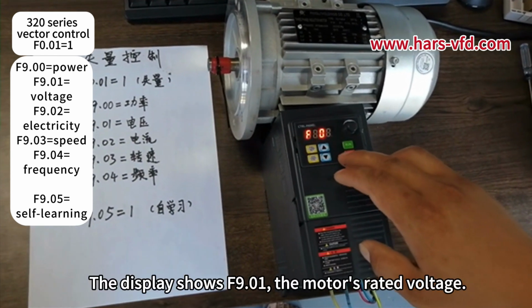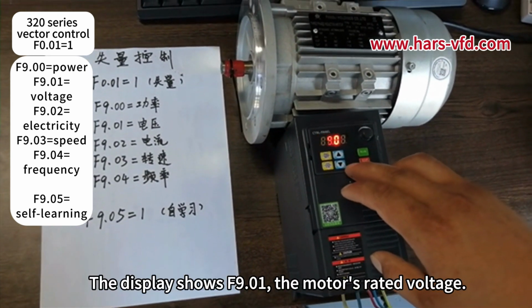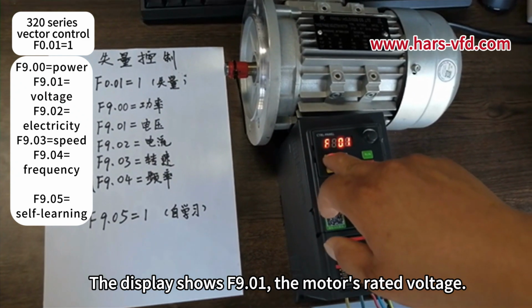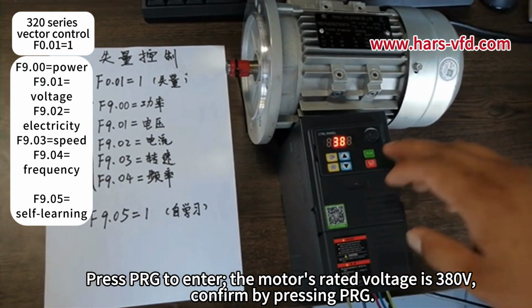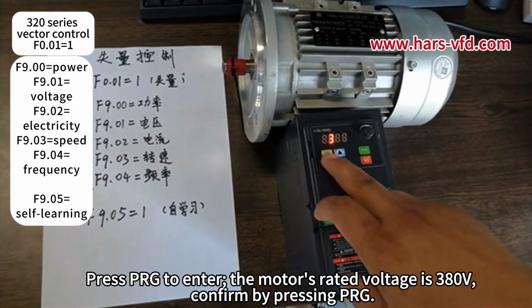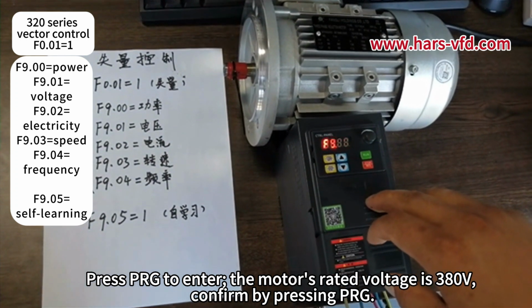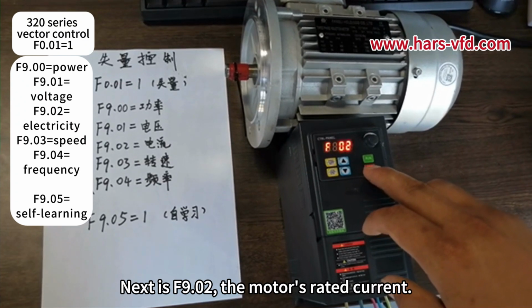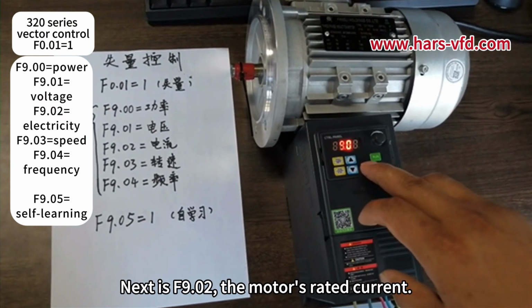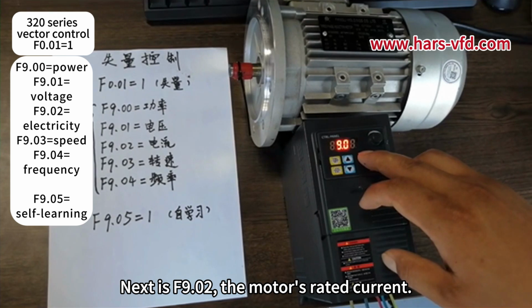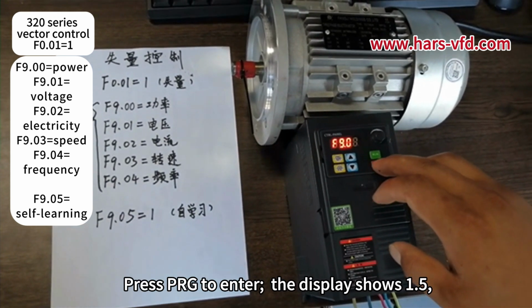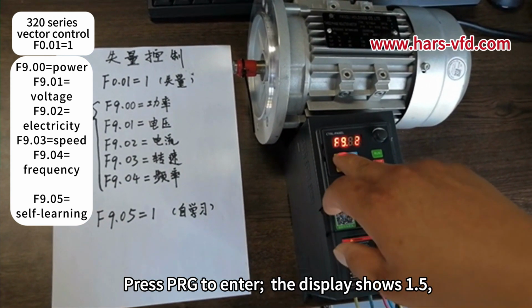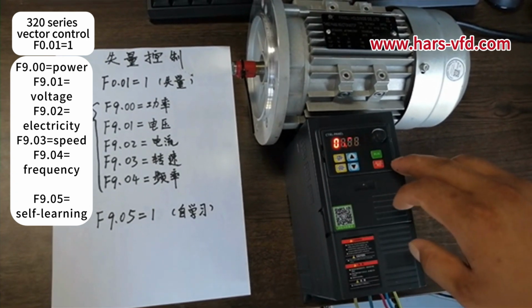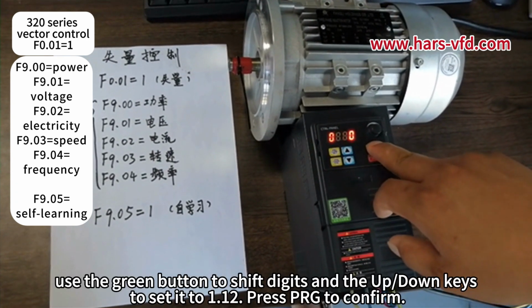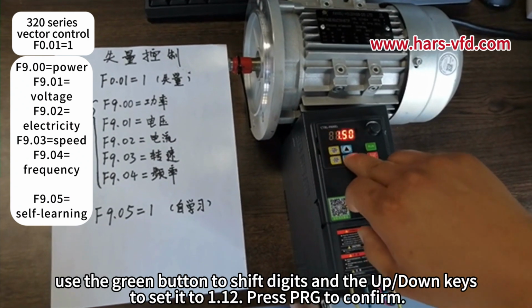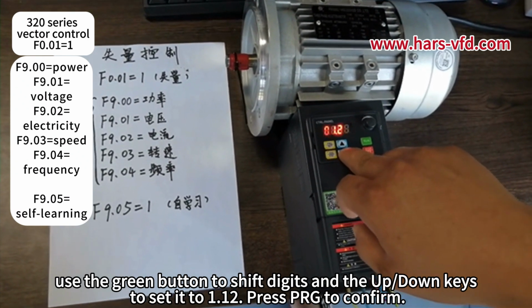The display shows F9.01, the motor's rated voltage. Press PRG to enter. The motor's rated voltage is 380 volts. Confirm by pressing PRG. Next is F9.02, the motor's rated current. Press PRG to enter. The display shows 1.5. Use the green button to shift digits and the up or down keys to set it to 1.12, then press PRG to confirm.